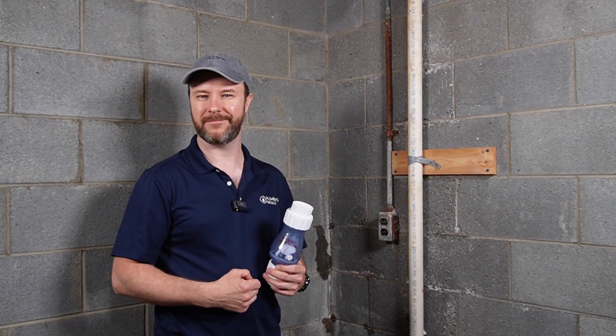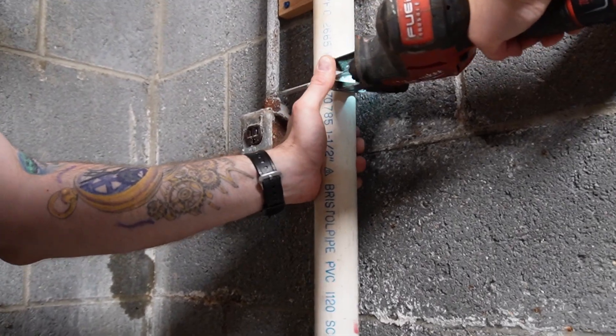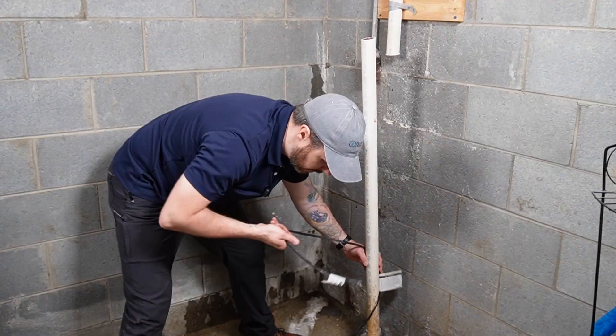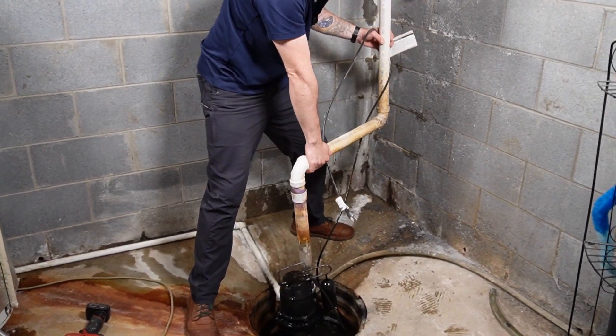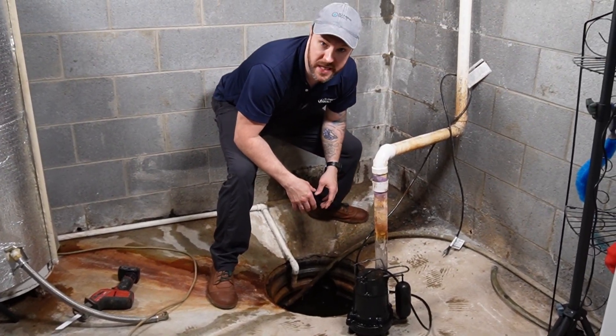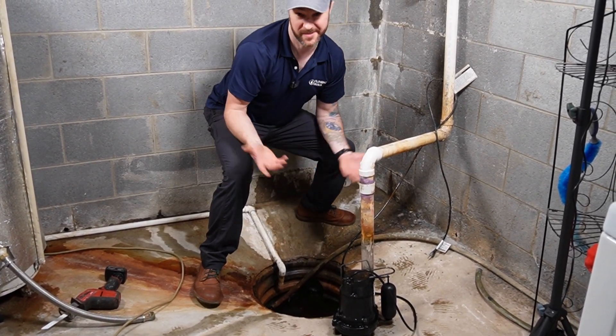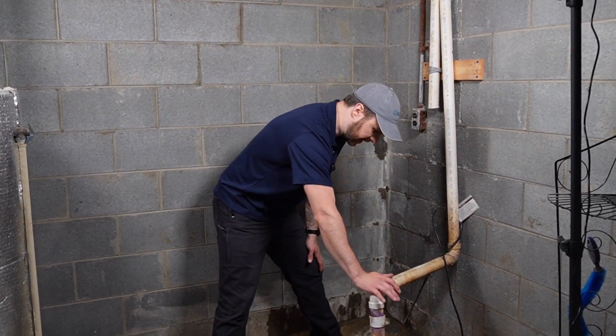I grabbed the Zoeller quiet check valve — it's clear, which is kind of fun because we get to watch it work. I'm going to use my Milwaukee hacksaw, it's a 12-volt. There's a lot of hard water in this area and they might even have the water softener discharging into this, which isn't great. Make sure you have an assortment of PVC fittings, PVC primer and glue. The one thing I want to make sure we have on this install specifically is a weep hole, which is going to be below the check valve close to our pump.